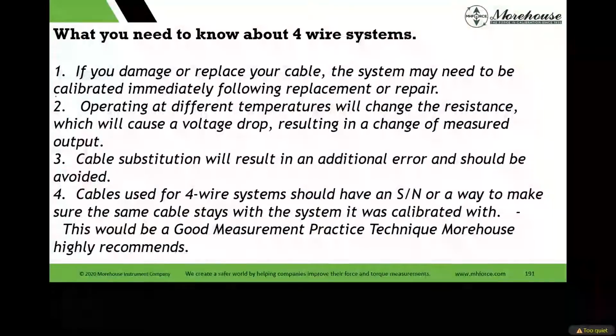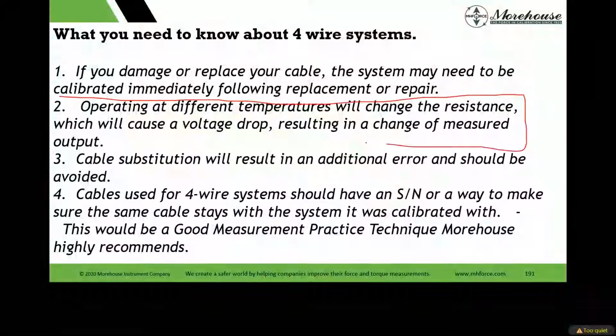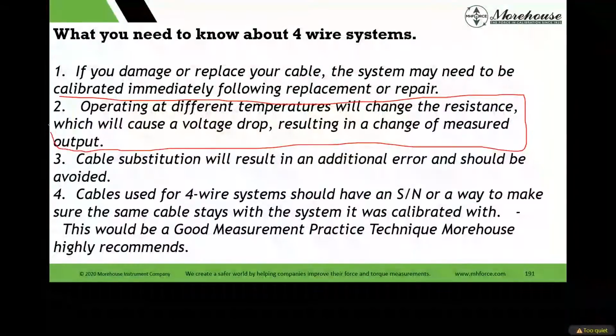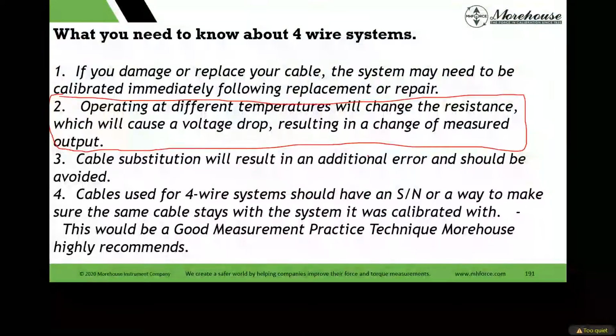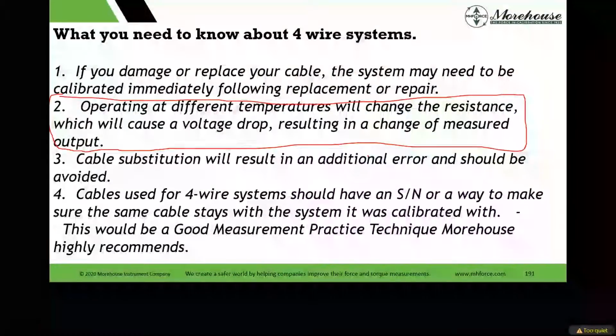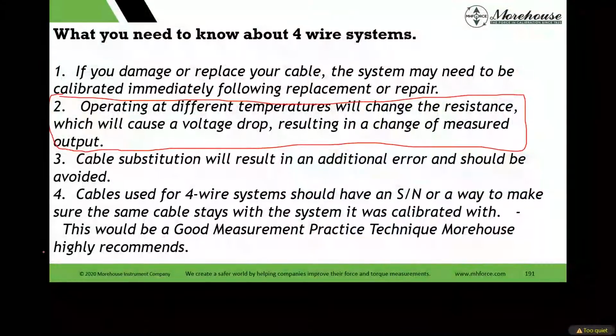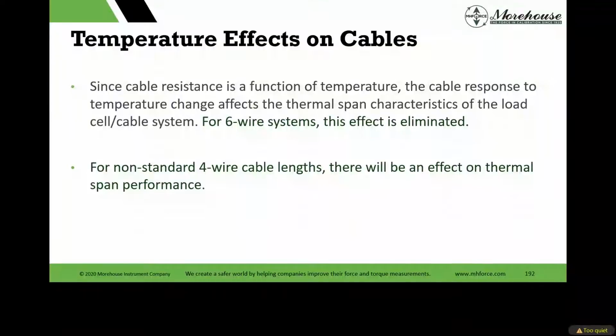Is this really that big of a deal? Someone might ask. No, not really. But it is something to consider. It's another variable that's out there on the temperature change in the 4-wire versus 6-wire. The length is huge. The change in length of the cables is just a gigantic impact from going from 6-foot to 10-foot. It's going to give you some large errors, and I have a slide on that.